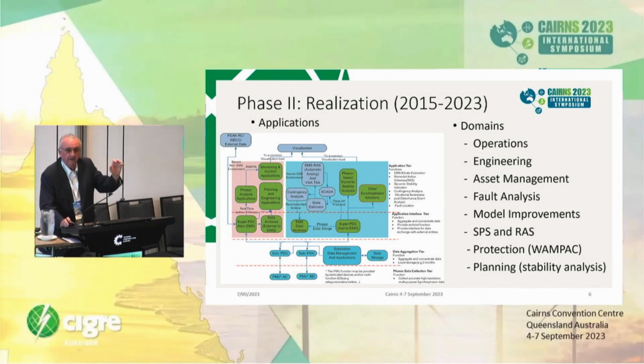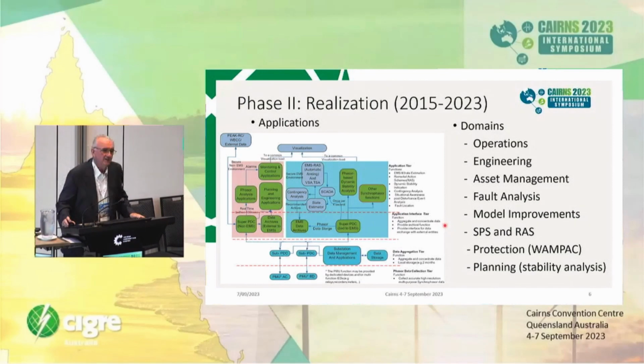Now remember one thing, because it matters a lot. This is primarily developed for monitoring phasors or deviations from phasors. And when we come to transients, real transients like faults and transients caused by inverters and stuff like that, the synchrophasors are having difficulty following some of these things. And there are some other developments along those lines that will take care of that. So that's that period. And then we're now looking at the future.